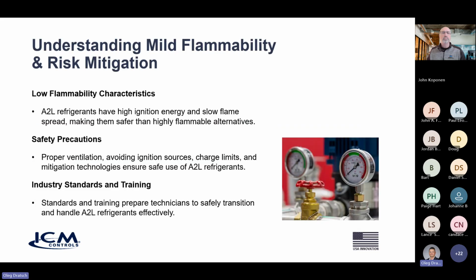So, like I mentioned, today's refrigerants are in the 2100 range for GWP, global warming potential, and the R454B and the R32 are down in the 600 range. So it's a better refrigerant for the environment, but the trade-off being mild flammability. We'll get into that a little bit more as we go through this. A2L refrigerants have high ignition energy and potential for low or slow flame spread. So while it's a safer alternative for the environment, it's a little bit more risky in home use, and the EPA has gotten together with ASHRAE and has set precedents on how the HVAC industry should be handling these refrigerants and what these HVAC systems need to do to mitigate any type of risk when there is a leak of the A2L refrigerant in your system.